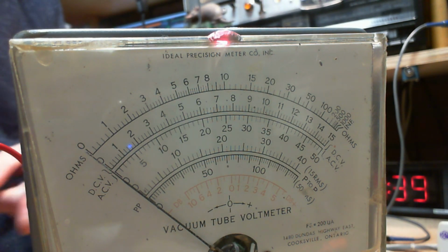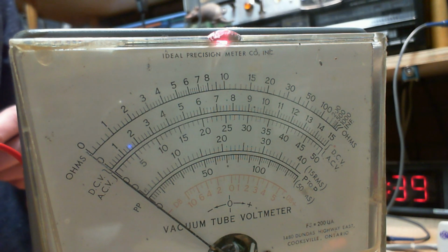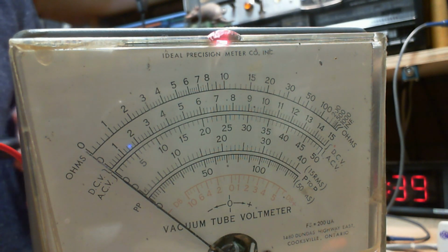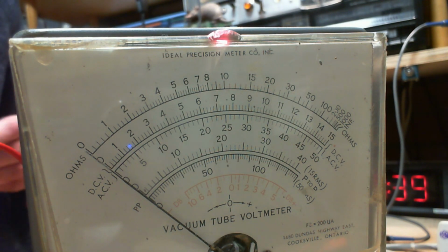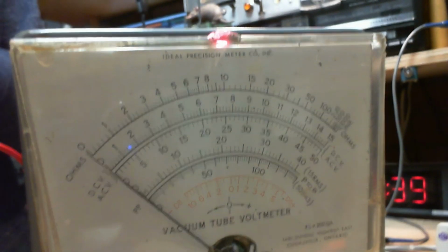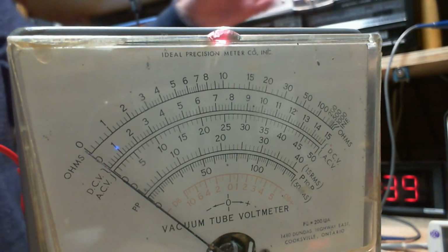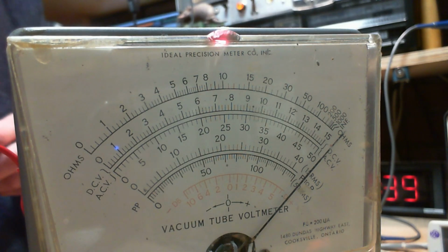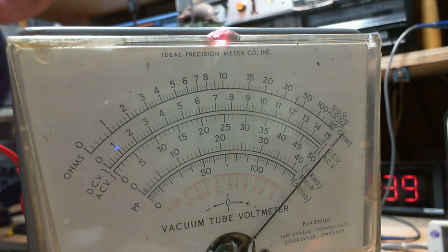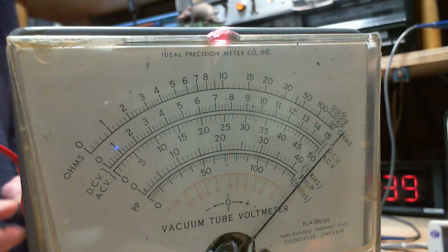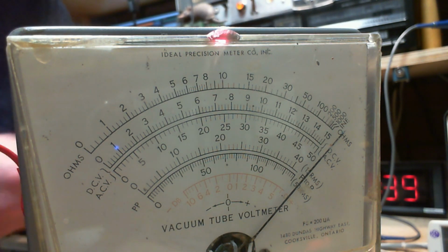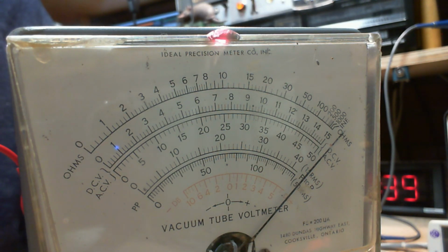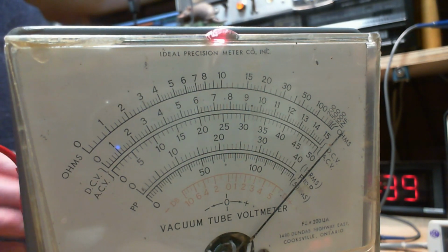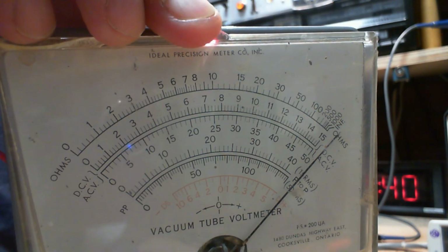So now the idea is to get this thing to read the correct voltage. The correct voltage is going to be around 123, I think. I think we're all set. I'm just doing the safety thing here. I'm sure we got everything hooked up. Yep. Voltage applied. And we want to crank that back to 123.7. That's what it is right now. Yeah, so I'm going to do an AC calibration adjustment, and then we'll do the balance. I just want to bring this roughly into its proper area setting here. Hold still, meter, don't go anywhere. There we are. 123, just roughly. Good.